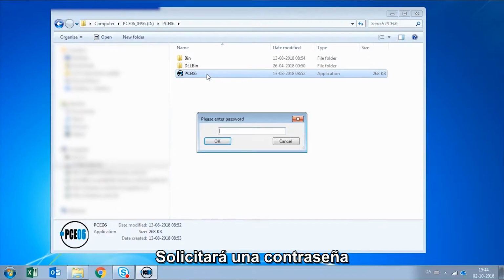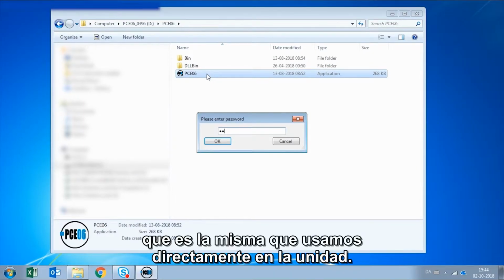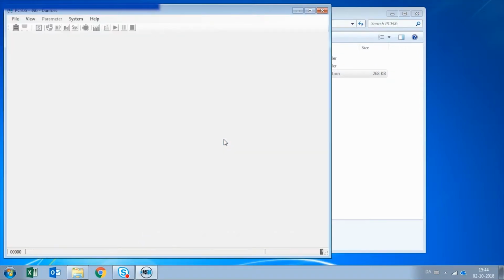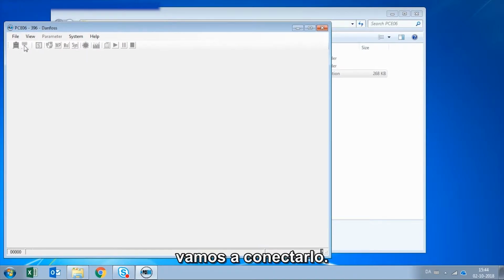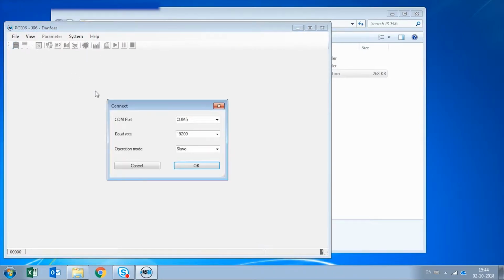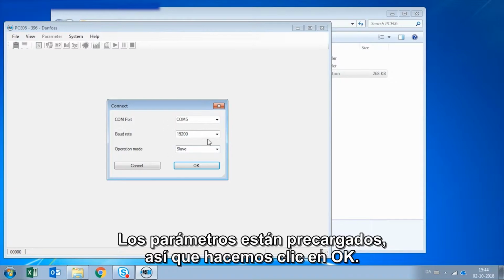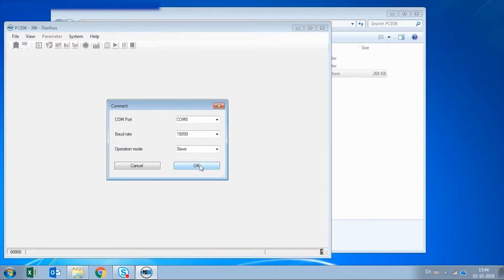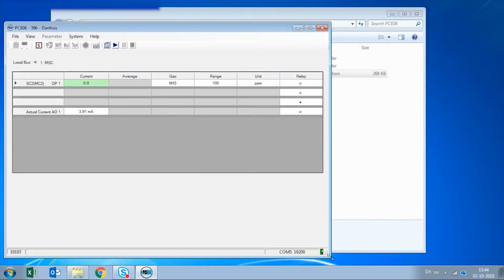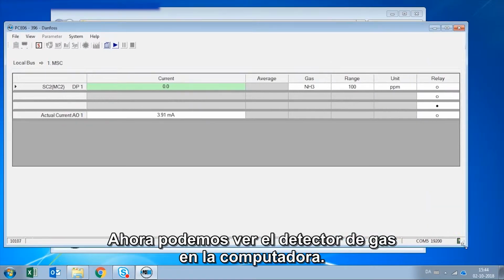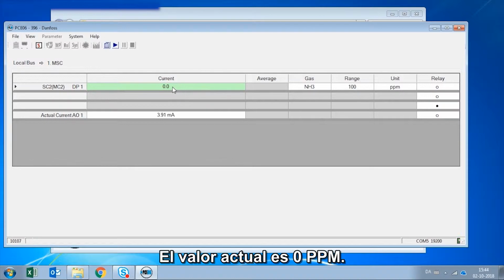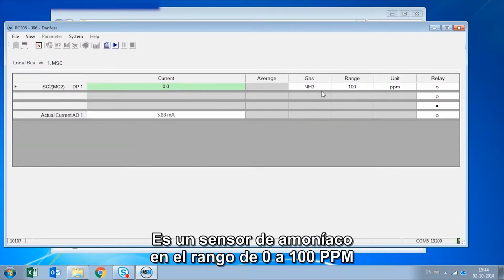It's gonna request a password, which is the same way as if we are directly operating a unit. And once the software has opened, we are going to connect it. Parameters are already preloaded, so we just click OK. And now we can see our digital gas detector on the computer. The current value is 0 ppm. It is an ammonia sensor on the range from 0 to 100 ppm.